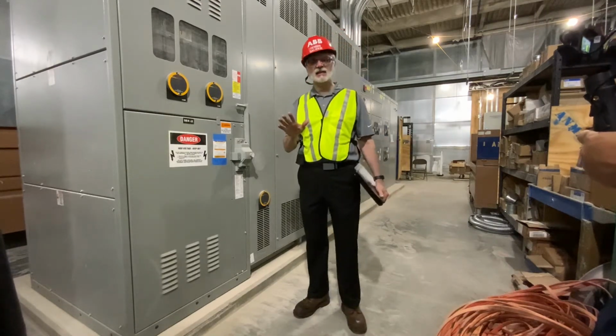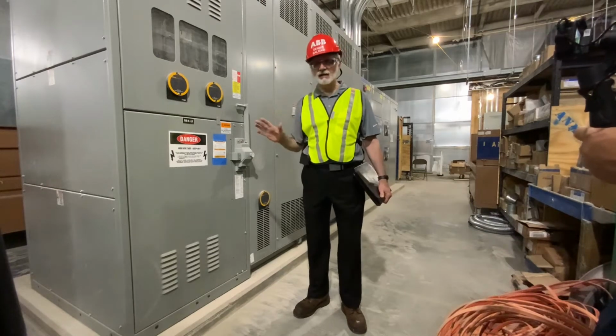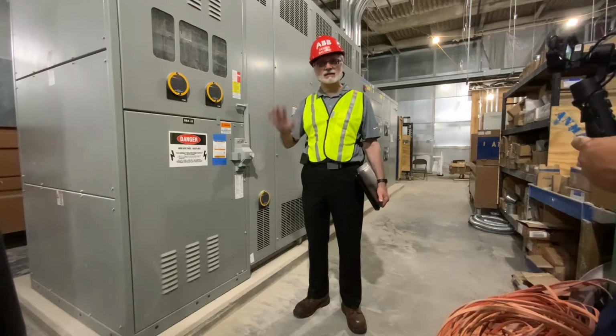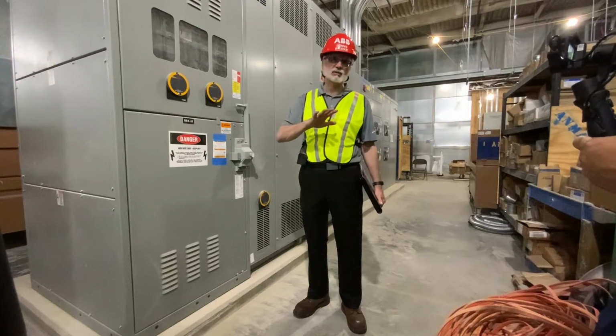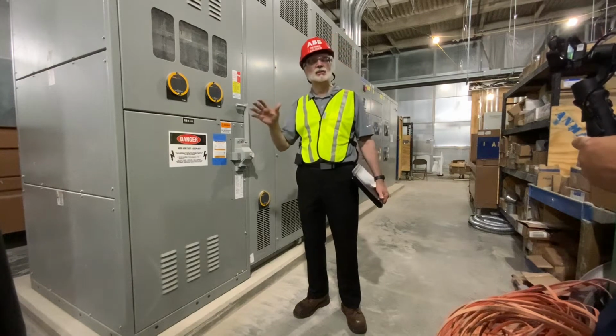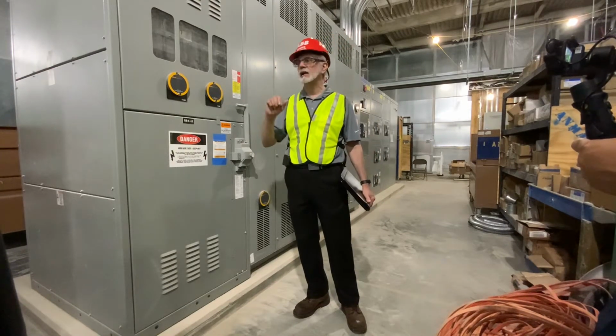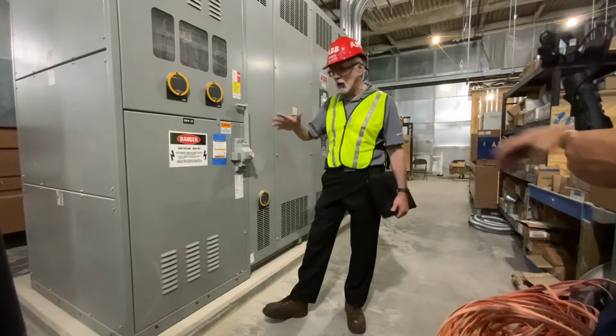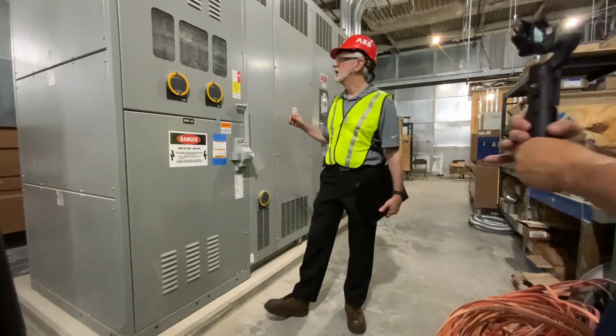Again, from a safety standpoint, we don't want to do any of this from an energized standpoint. We want to de-energize the equipment, not just when we're doing maintenance, but also when we're doing any kind of testing and inspection. And we'll go through each part of the substation one at a time.